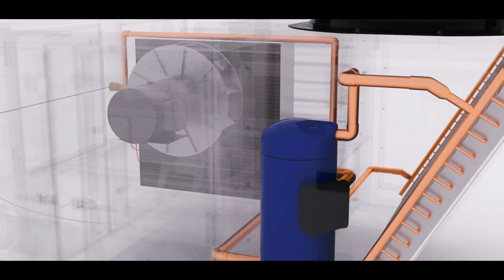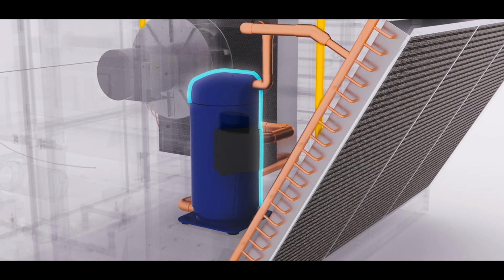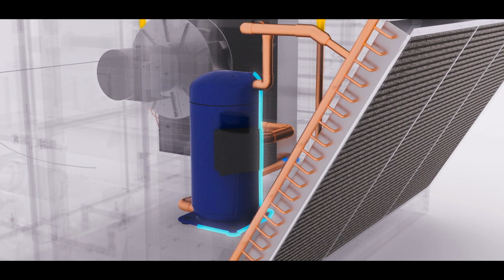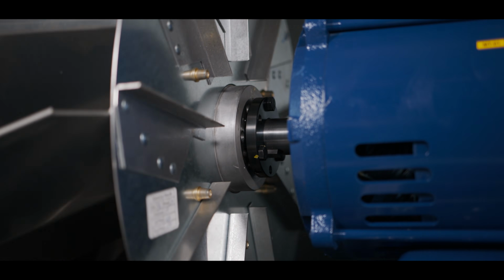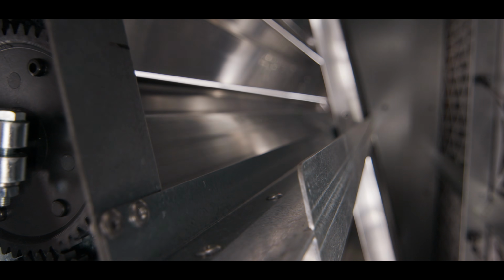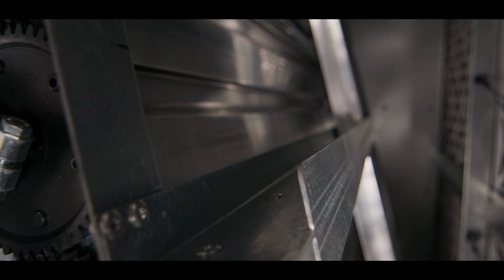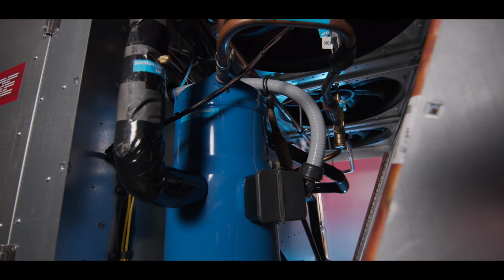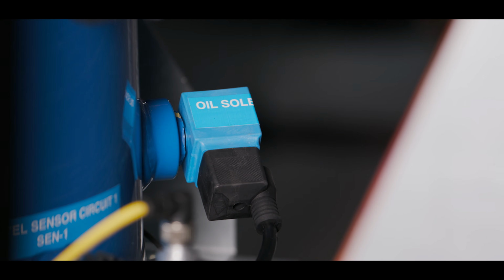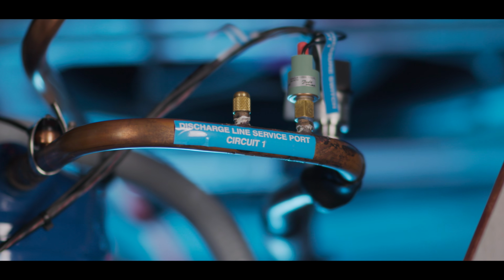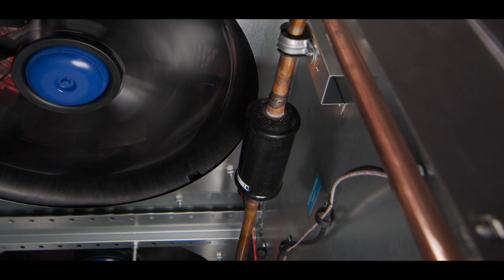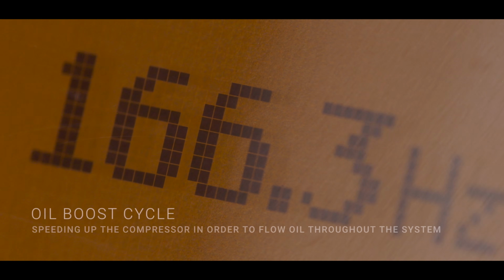Just the compressor itself, we had to figure out how to throttle it, how to ramp it up, how to slow it down, how to manage refrigerant in the off cycle. Believe it or not, what happens when the unit is off is almost just as important as what happens when it's running. One challenge with variable speed compressors is oil management, and how do you keep oil circulating through the system, and ensure any oil in the system gets returned to the compressor?